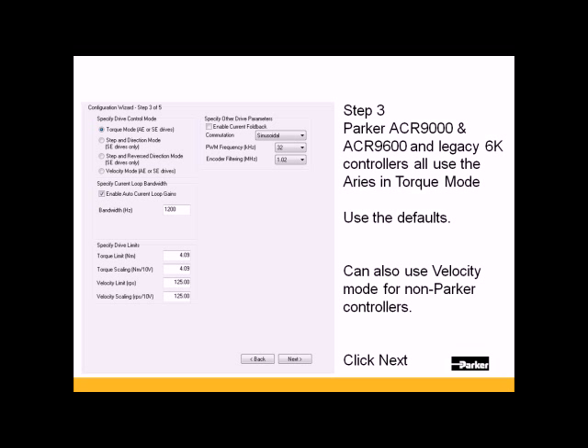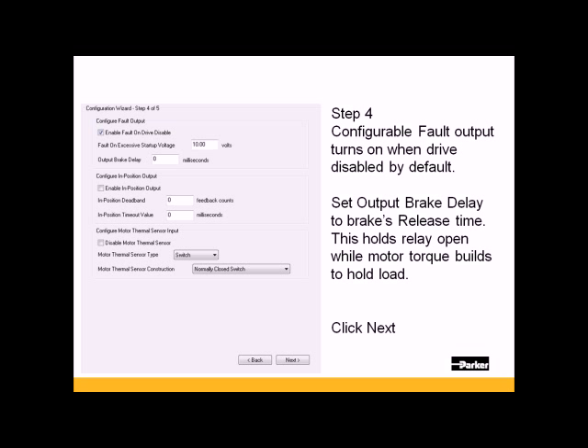Step 4, the fault output turns on by default when the drive is disabled. If you want that turned off when the drive is disabled, you can uncheck the checkbox here. The output brake delay, you can set this to the brakes release time. This will hold the relay open while the motor torque builds to hold the load in vertical applications. Click Next.